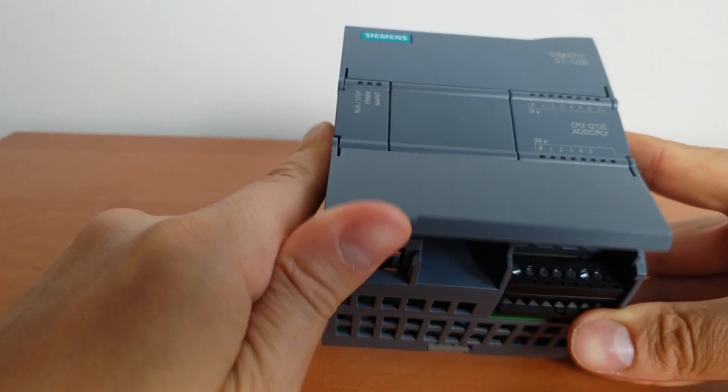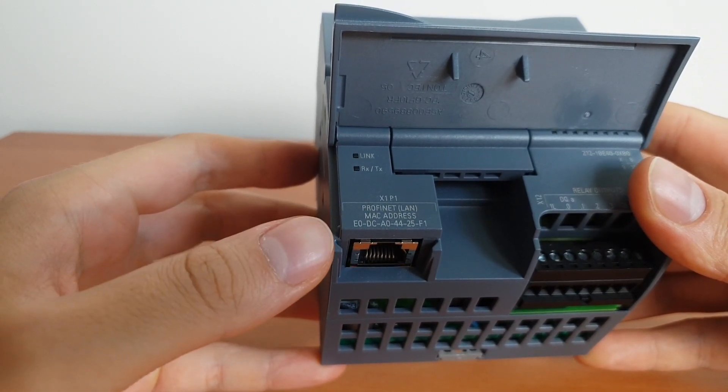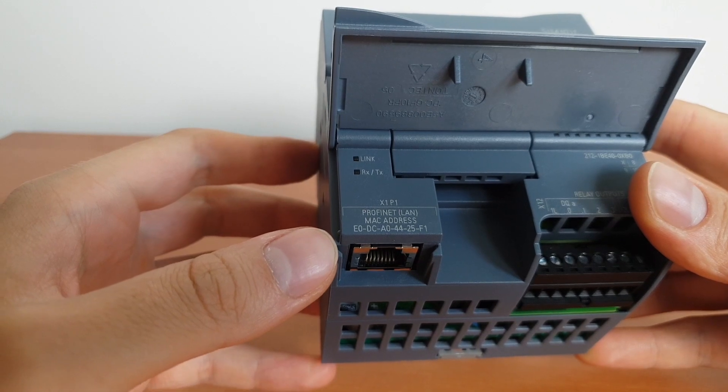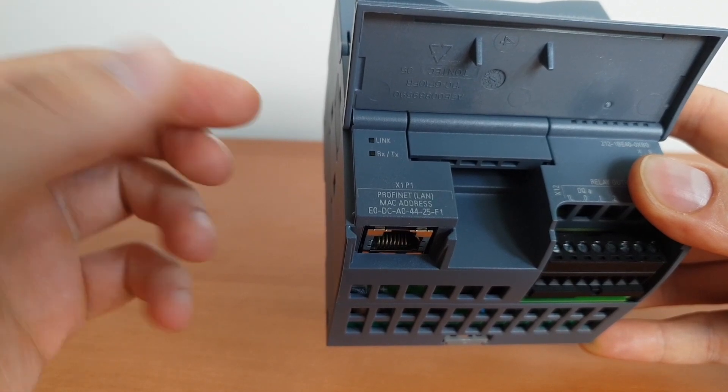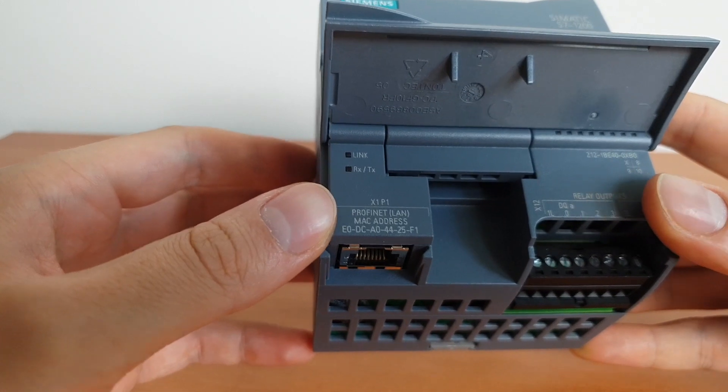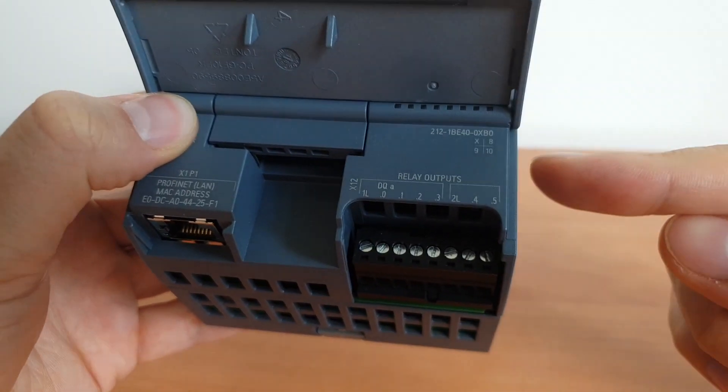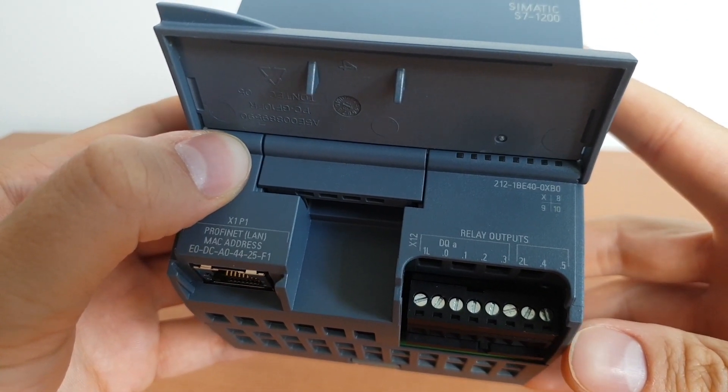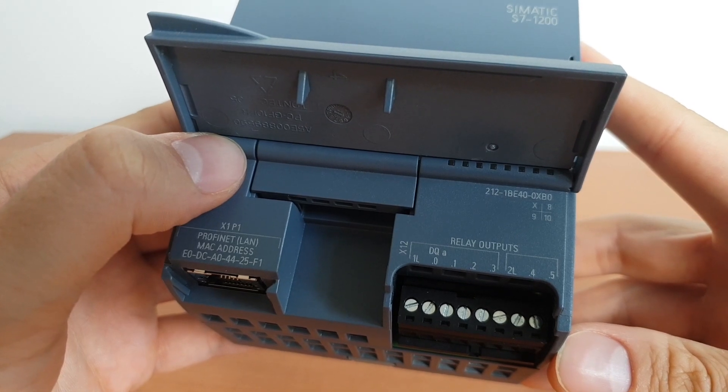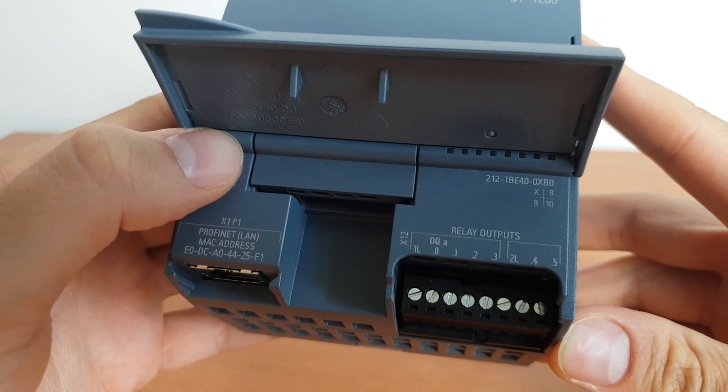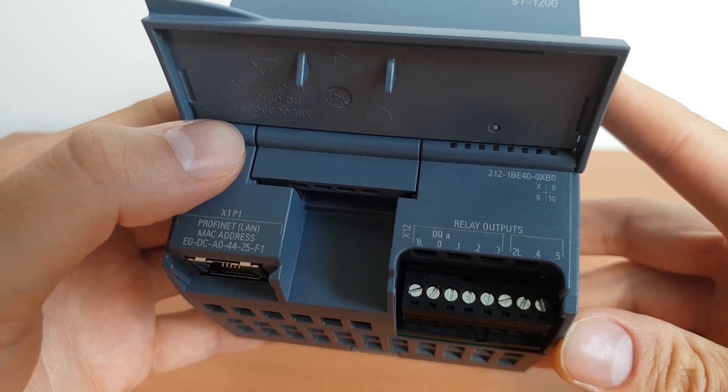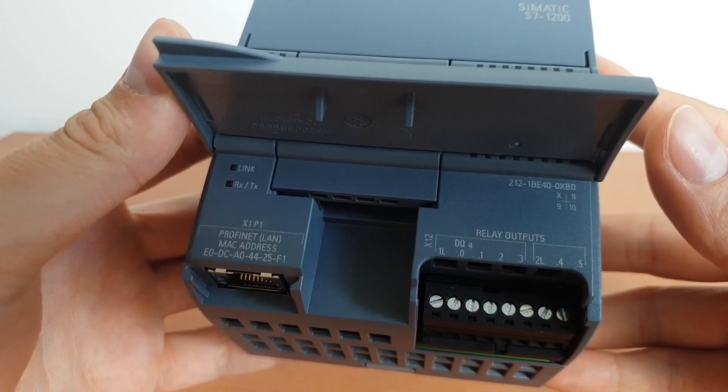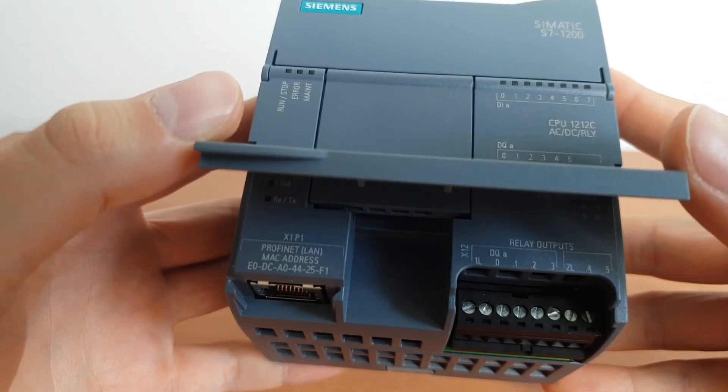The last two things are this socket we're going to use to communicate with this PLC. We're going to connect a normal ethernet cable here, and it can also be used for PROFINET communication. And the last thing is this set of digital relay outputs. We have two groups of outputs here, from zero to three and from four to five, and we can use two different voltages for each group or even two different types of voltages, AC and DC.